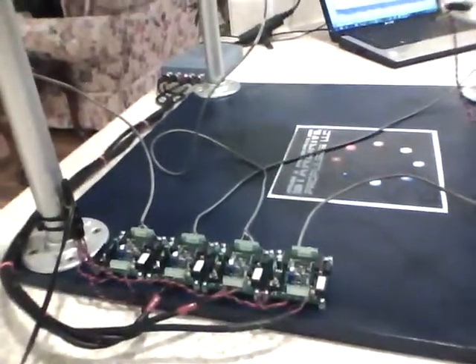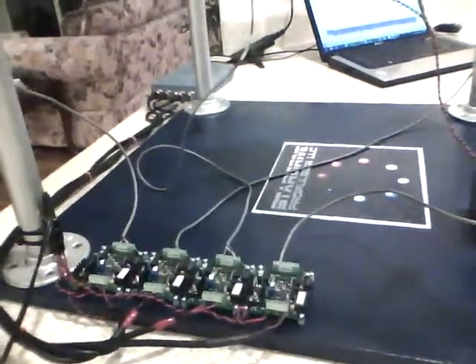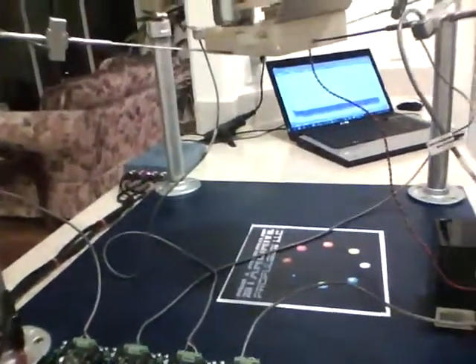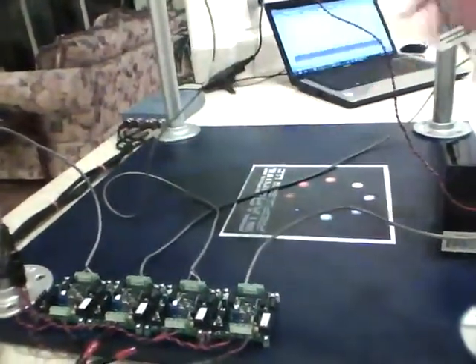I went back and zeroed all of them to zero again. You have a balance control on each driver board. Explain how you balanced each one of these control mechanisms so that they read zeros at the beginning of the test. It really doesn't matter where I set them, just as long as they're all set alike.